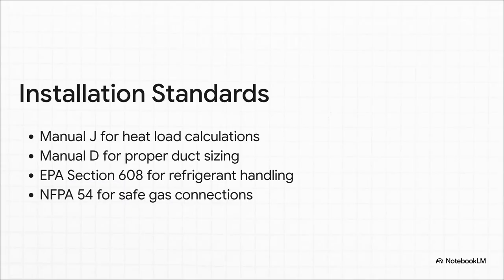Now, if you do cross that threshold and absolutely must replace the system, the required technical standards prove exactly why you need a certified professional. Proper installation isn't guesswork, it is an exact science. It requires a Manual J calculation to measure exact heat loads, actually taking your insulation and windows into account. It requires a Manual D calculation to ensure duct sizing perfectly matches airflow requirements. Without these, an oversized unit will just short cycle and fail to dehumidify your house, while an undersized unit will run continuously until it literally works itself to death. Add in strict EPA and National Fire Protection Association standards for handling refrigerants and natural gas, and, well, you quickly realize just how precise this engineering really must be.